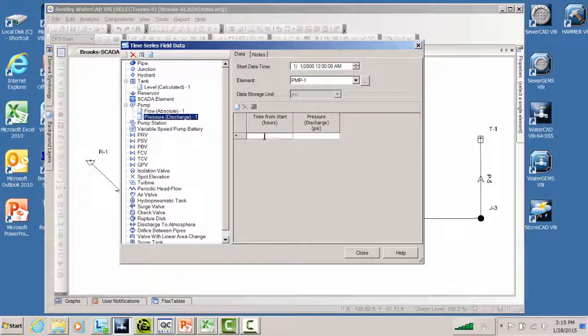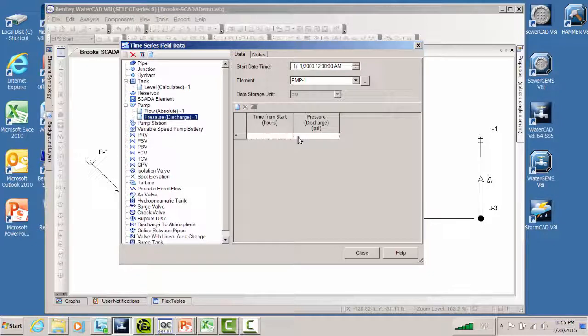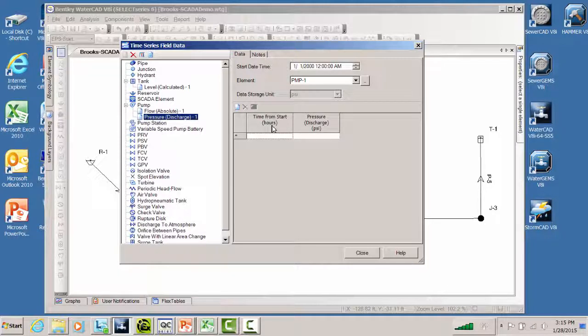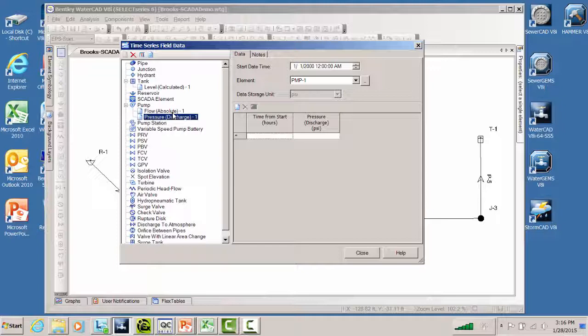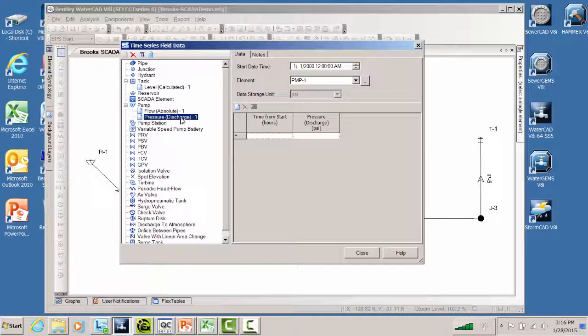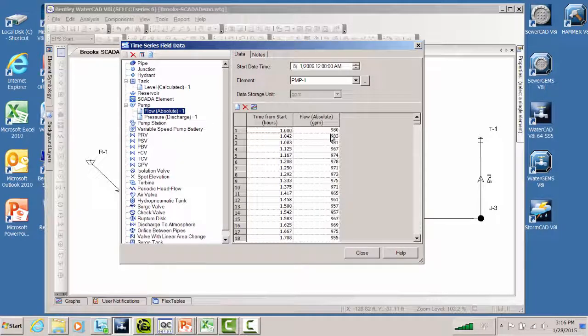And then I would go out to the data source, and I would usually use copy, paste, copy and paste the values in from the original data source to this model. Now, notice this is saved as time from start, so we need to have the fields identified relative to time from start, not the date and time format. We will be able to get that when we get into the actual graph. So this is how we create this data and make this association and fill these tables up with the actual data that came in from the SCADA system.